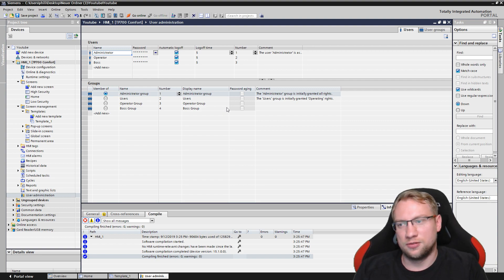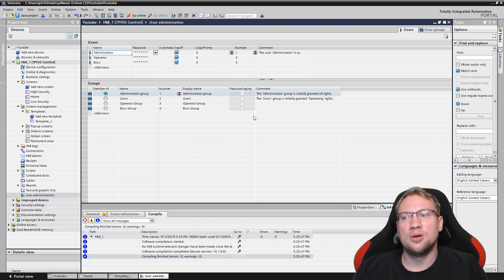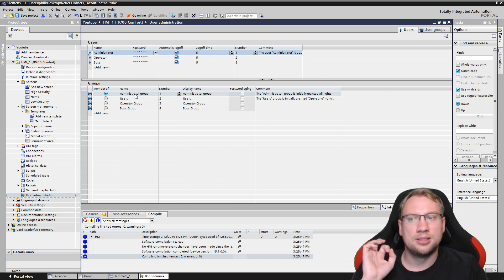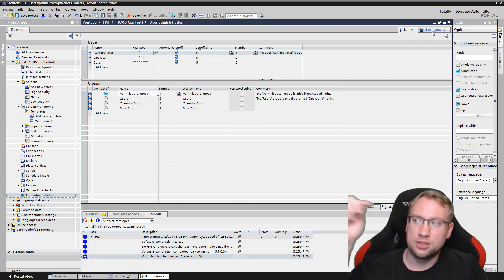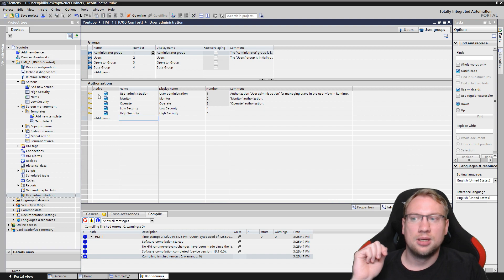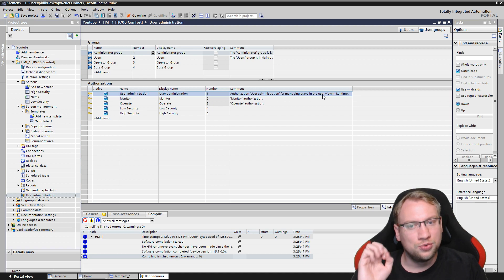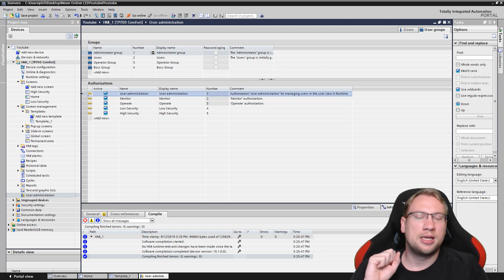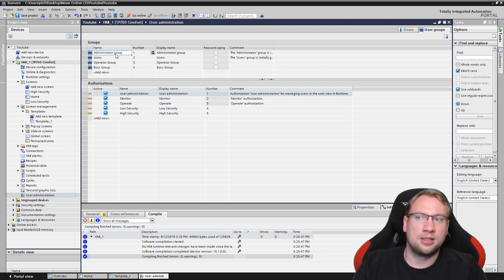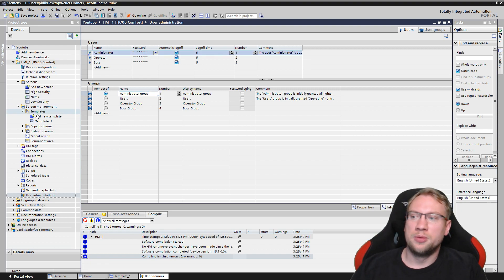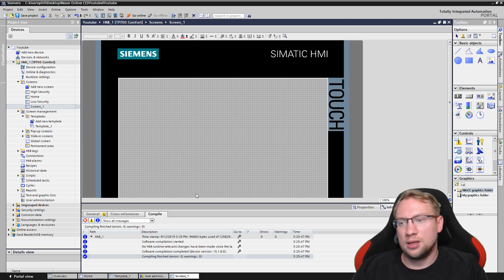We should also have a user view — that's what it's called — on the HMI itself. The only thing we need is the administrator user. He's in the administrator group, and the administrator group has all rights. Especially important is the user administration authorization, for managing users in the user view at runtime, and it's automatically active for the administrator group.